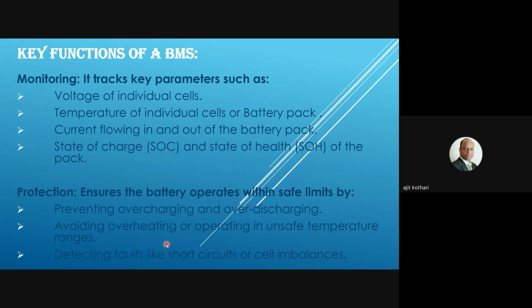Then the overheating operating temperature - lithium ion batteries have a certain range of temperature where they perform, or operate at maximum efficiency. Once that temperature exceeds the limit, there is a danger of explosion, or smoke will come from the battery. To avoid that, this over temperature sensing is also part of BMS. Once it reaches that unsafe temperature, it will immediately cut off the load, either charging or discharging - the MOSFETs will get switched off, and the battery or battery bank is safeguarded from overheating.